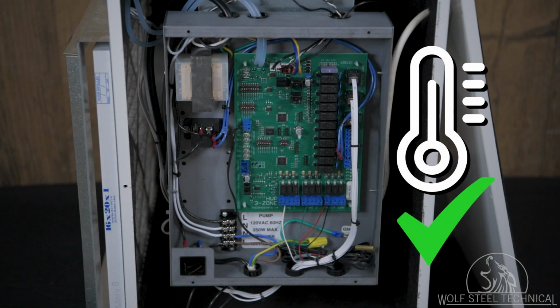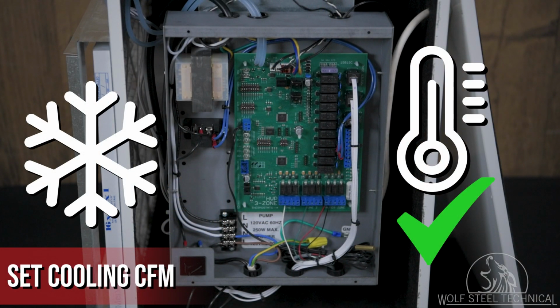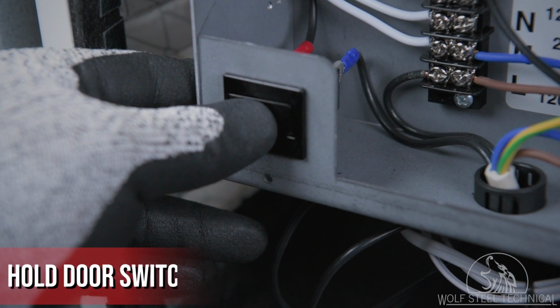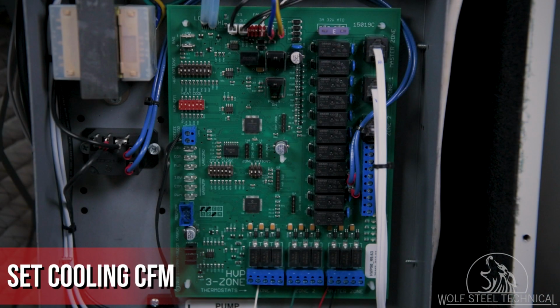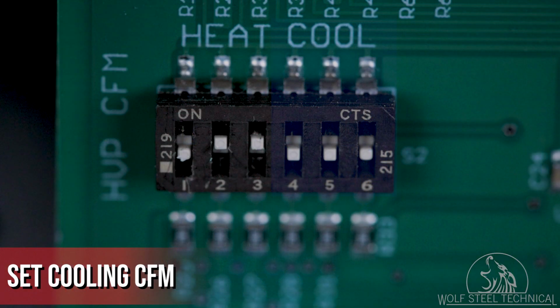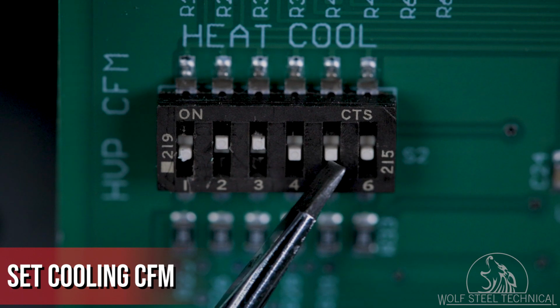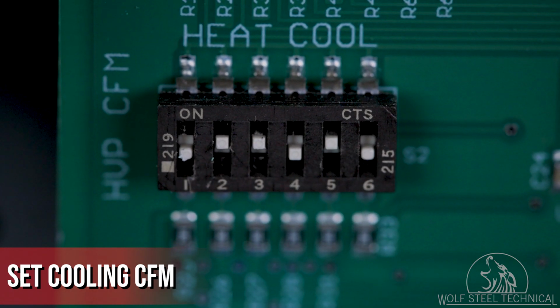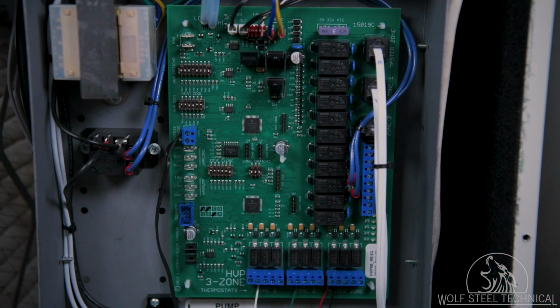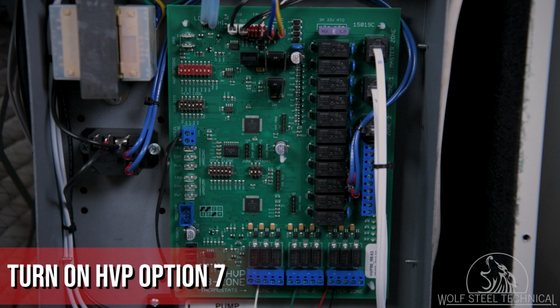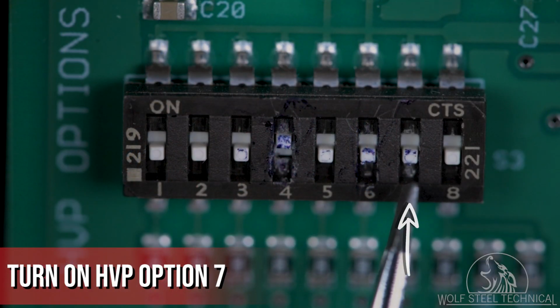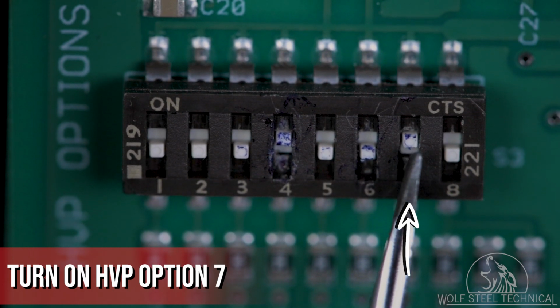Regardless of whether the system has cooling or not, it's important to set the cooling CFM to ensure the system continues to operate as intended. Ensure the door switch is being pushed in and turn your attention back to the HVP CFM switches and identify cooling switches 4 through 6. Refer back to the CFM chart in the product manual and set the switches to achieve the correct cooling CFM for the installation. To calibrate for the cooling speed, turn your attention back to the HVP option switches and set the HVP option 7 switch to on.